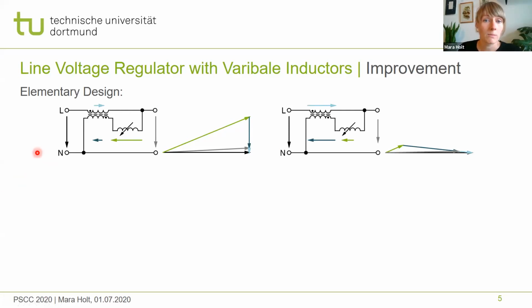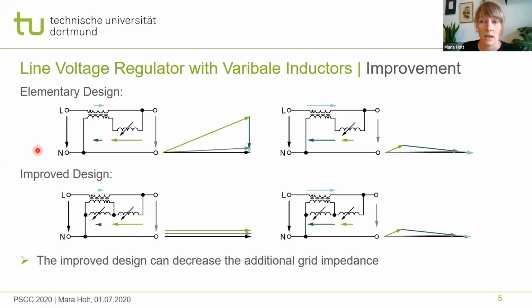To avoid the grid impedance increase, a significant improvement was developed in our previous studies. A second variable inductor is connected in parallel to the series transformer. By a maximal reduction of its inductance, the series transformer is nearly short-circuited, and therefore it bypasses the influence of the transformer's magnetizing reactance. As you can see, in the initial state the input and output voltages are nearly similar, whereas the control range stays the same. We built this kind of setup in the laboratory.